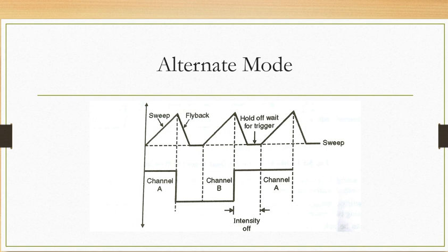So let us discuss the drawback of this as well. What is the drawback of this? The two traces are not there at the same time. When different signals are displayed on each channel, they are not displayed together simultaneously. If you see, these two traces are not there at the same time.